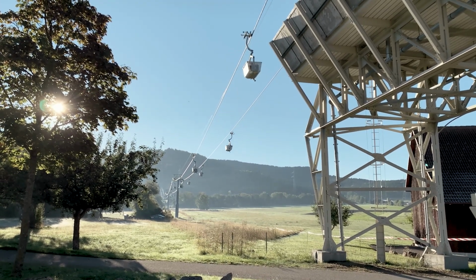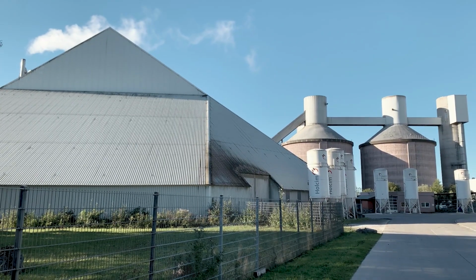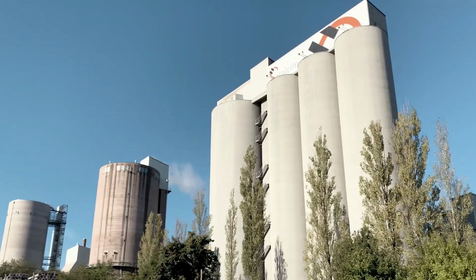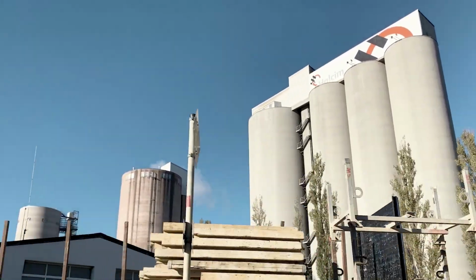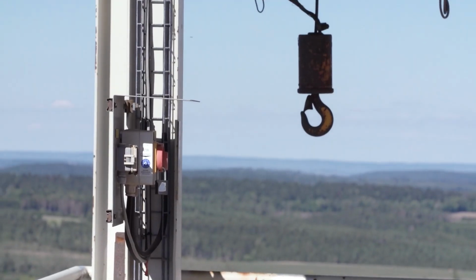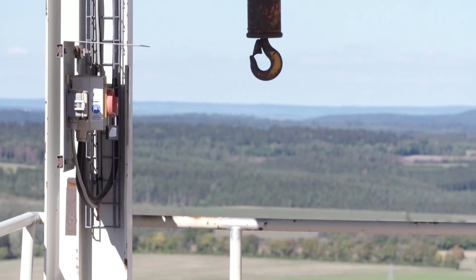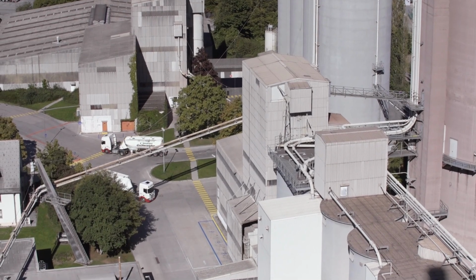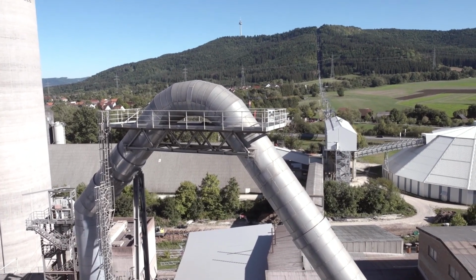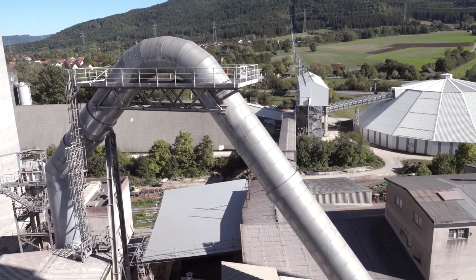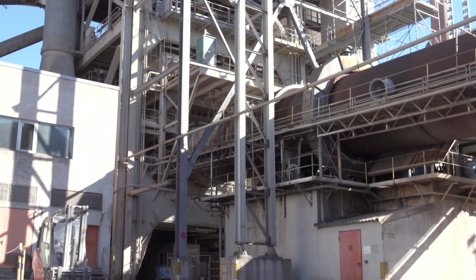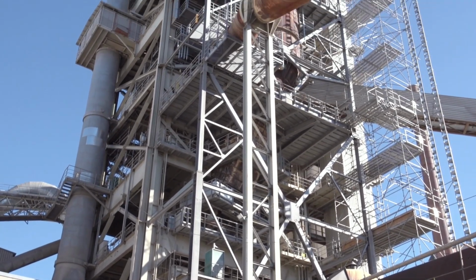With the Testo 350, you can easily and efficiently perform exhaust gas measurements on industrial plants, for example exhaust gas analysis on cyclone preheating furnaces in a cement works. The cyclone preheaters here consist of 4 cyclone stages arranged one above the other in the tower, which is about 100 meters high, and through which the exhaust gas from the actual furnace flows from bottom to top.